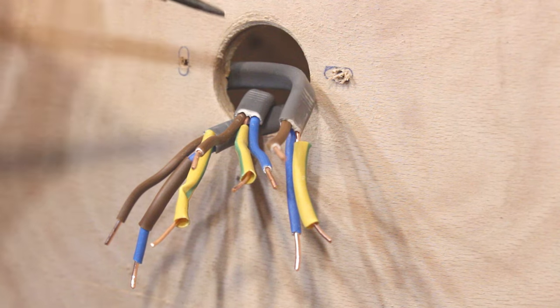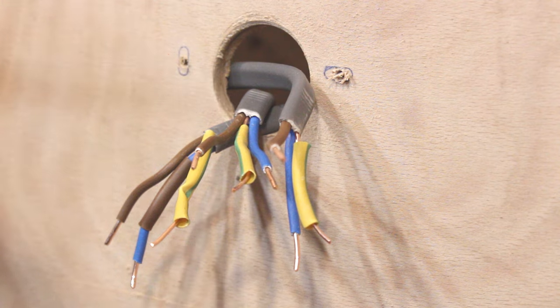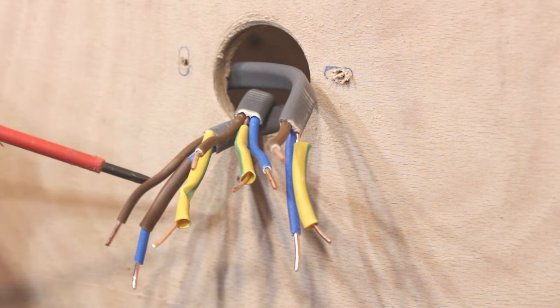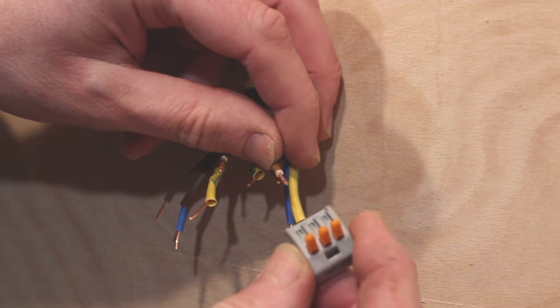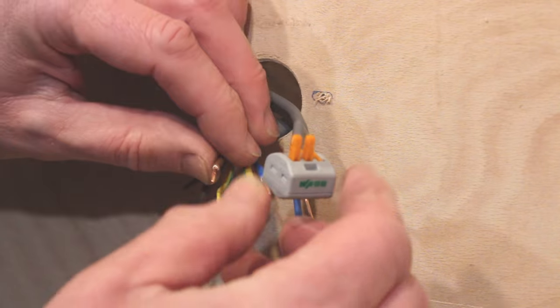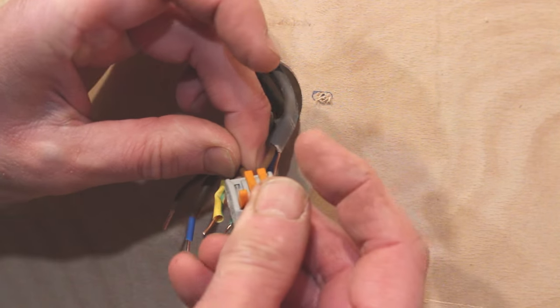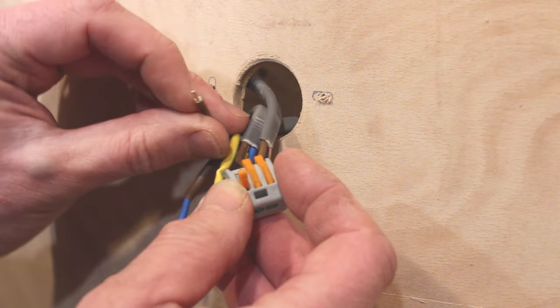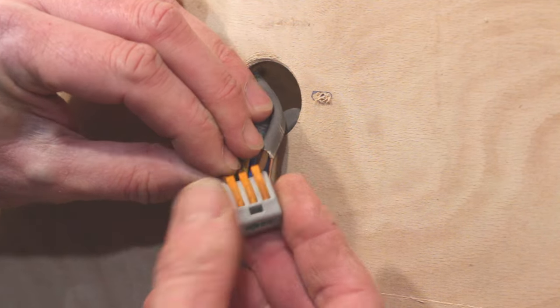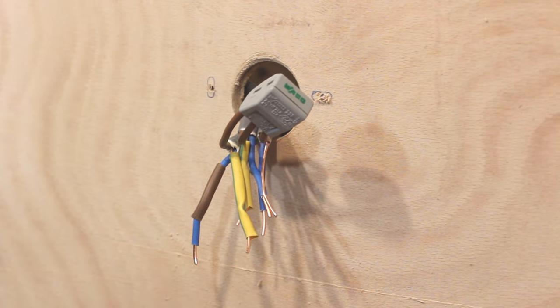So now we're ready to actually take the WAGO connector and connect up the live from the two lighting circuit wires and also the permanent live on the switch wire. So take your WAGO with the three-way connectors on it and put in the live from the lighting circuits. Make sure it's fully inserted. Clamp down and then the permanent live from the switch. Again make sure it's fully in. Close the clamp, give it a good tug. So just bend it back out of the way ready for the next stage.